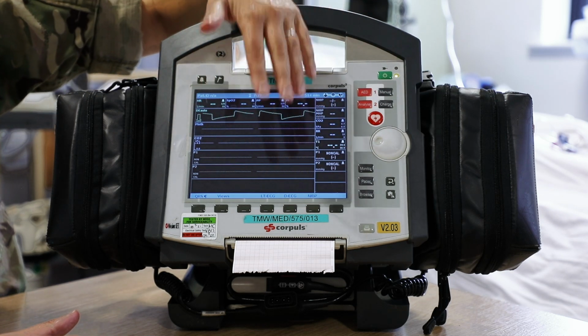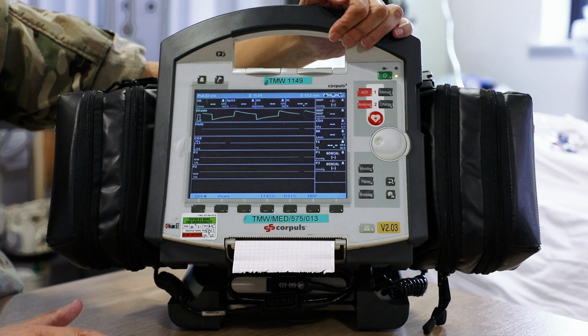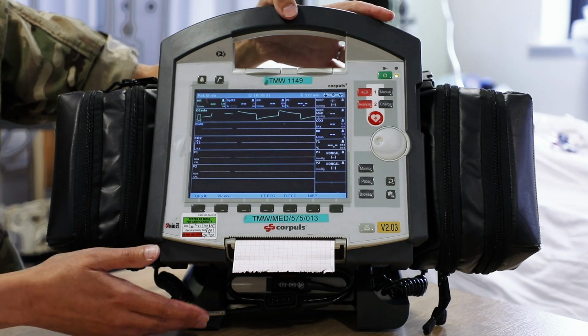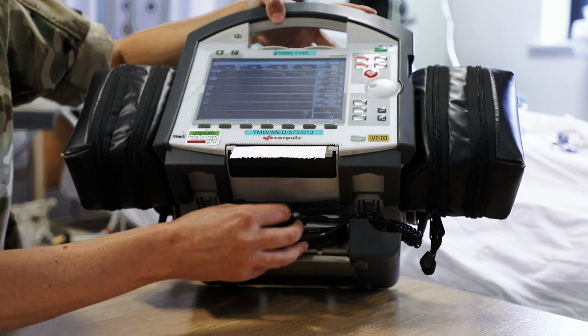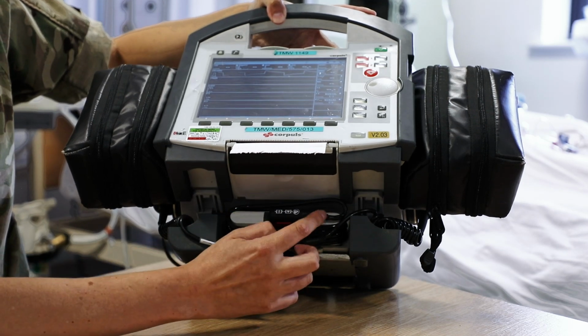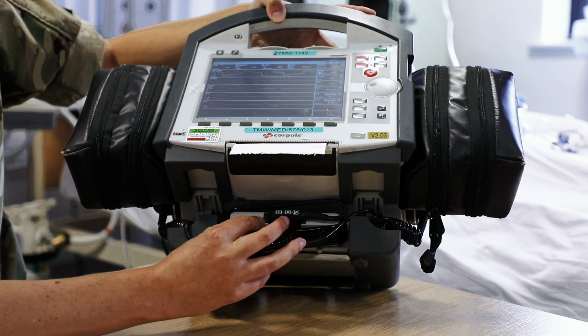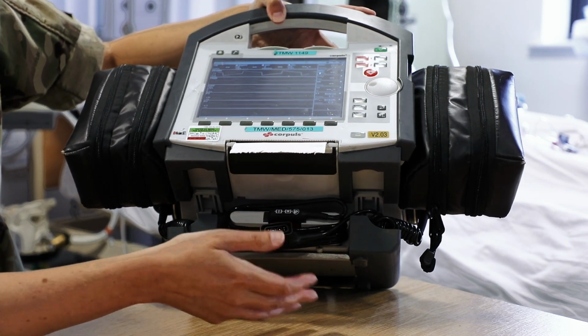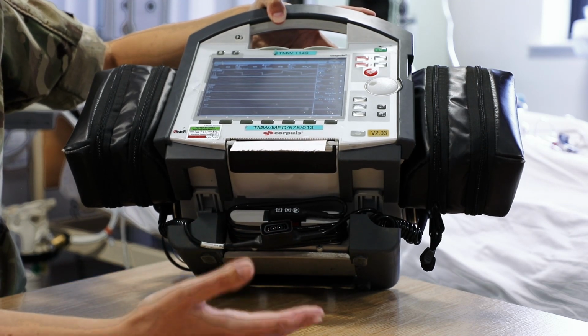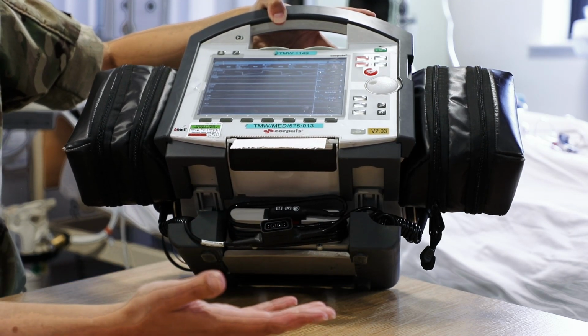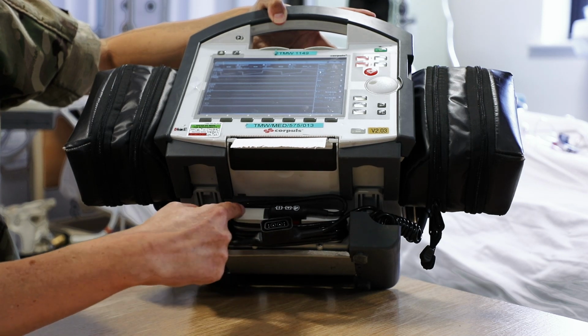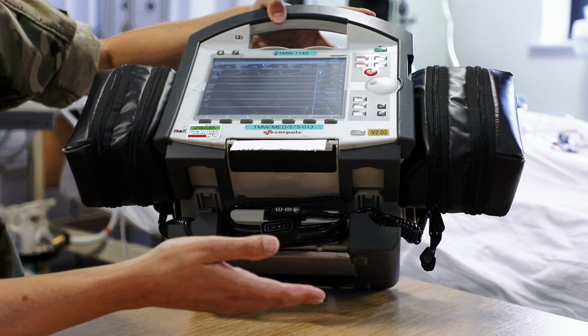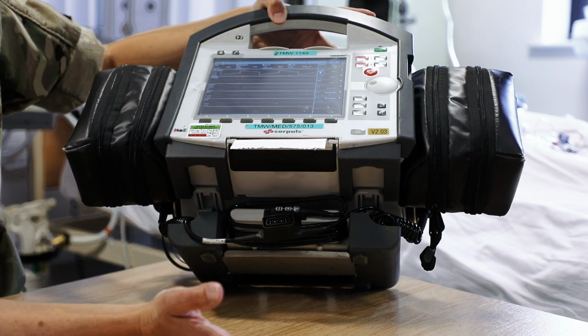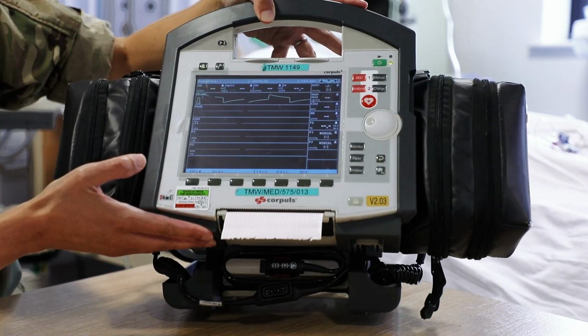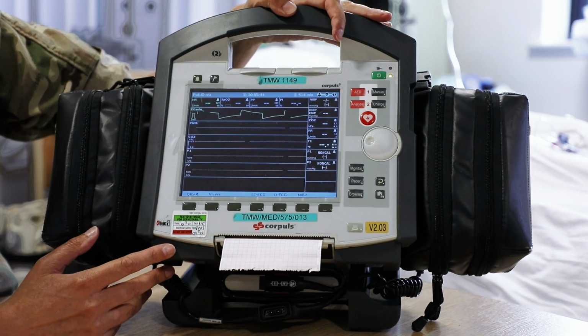This is the safe screen. This defibrillator isn't active at the moment, so we're going to just double check that our red master cable is seated correctly. This housing actually simulates a defibrillator box, similar to the external boxes that you attach in hospital. This is our test and dumping box. So just make sure that your red master cable is seated correctly and move into test number 2.